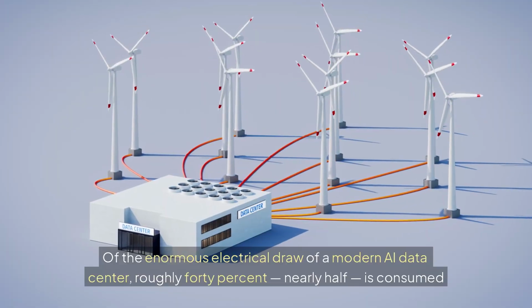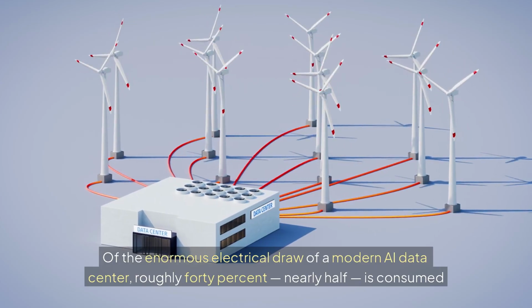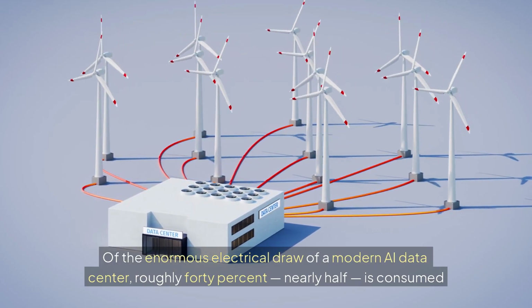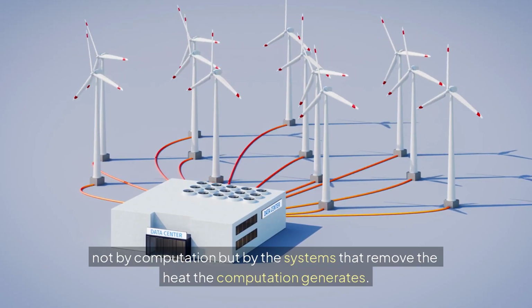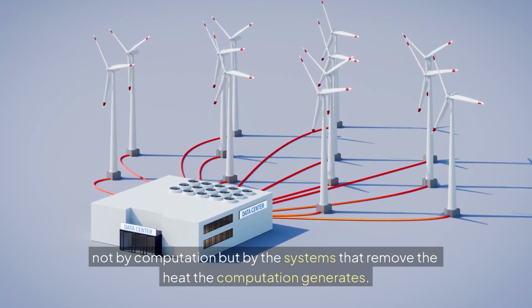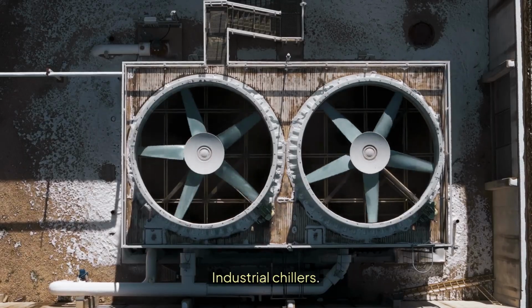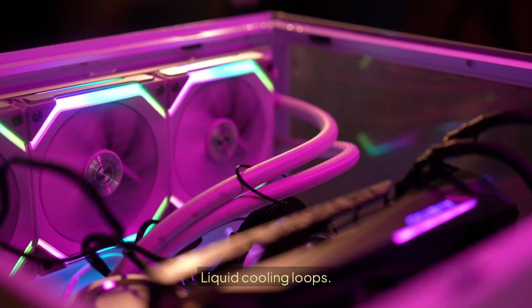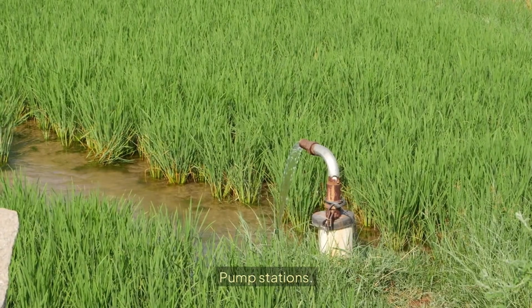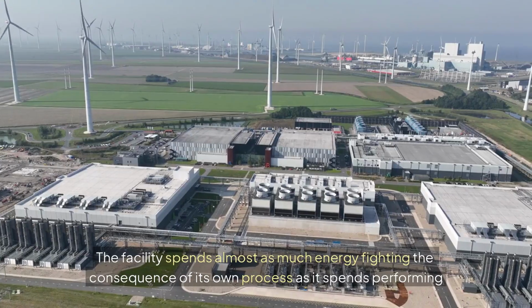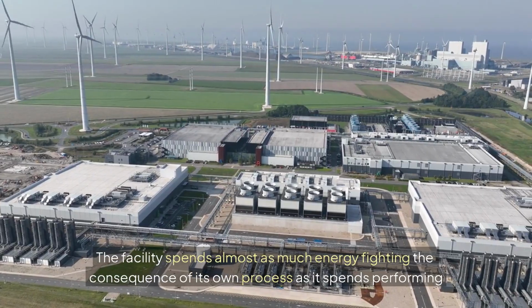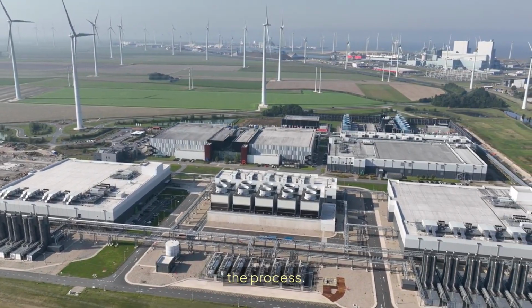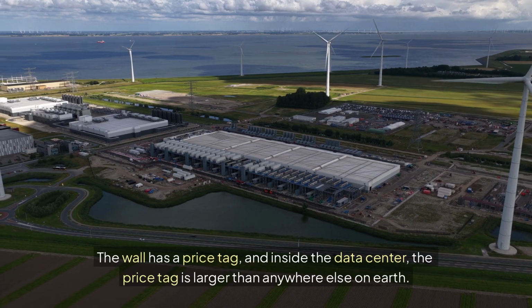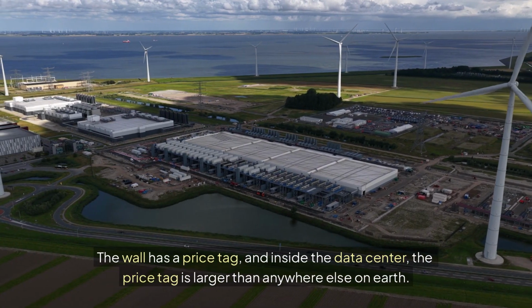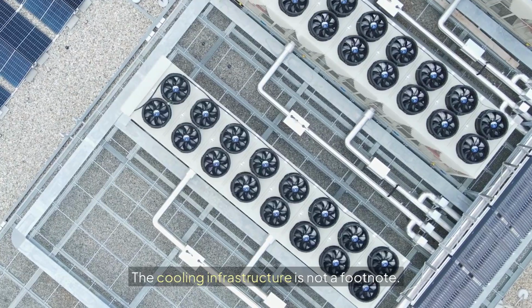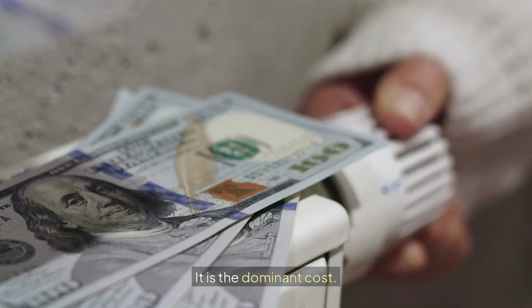Of the enormous electrical draw of a modern AI data center, roughly 40%, nearly half, is consumed not by computation, but by the systems that remove the heat the computation generates. Industrial chillers, massive air handlers, liquid cooling loops, pump stations, cooling towers. The facility spends almost as much energy fighting the consequence of its own process as it spends performing the process. The wall has a price tag, and inside the data center, the price tag is larger than anywhere else on Earth. The cooling infrastructure is not a footnote. It is the dominant cost.